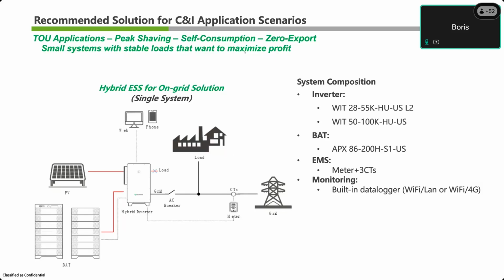One of my last points is to show what these systems look like, and I think this really illustrates just how simple the systems can be. I have here a simple on-grid solution, single system. So there's one inverter, one battery. And on that battery, we have our grid input, our PV, battery, all going into our inverter as a centralized location. There is no backup load in this system. So this would be useful for time of use applications, peak shaving, self-consumption. You can do zero export with this system, of course. And yeah, it's just a really simple solution. All of this can work without the other. So let's say you don't have PV and you want to use a time of use application. You can do so and just take the PV out and just connect the battery to it, and the inverter's fine with that. I'll keep going just to show some more.